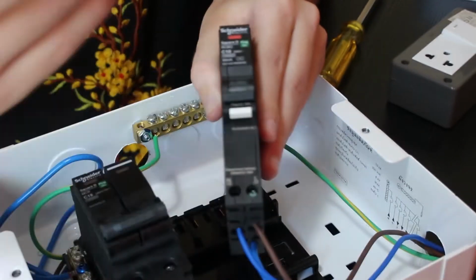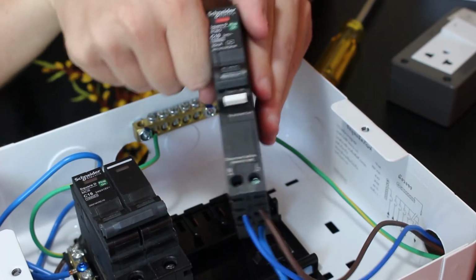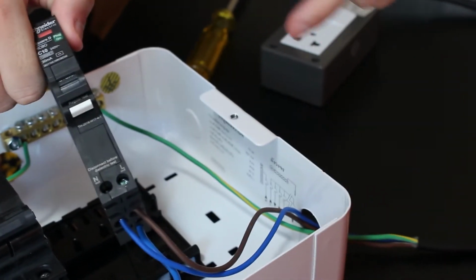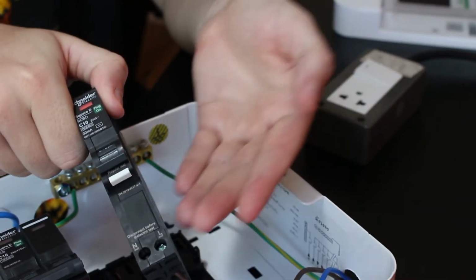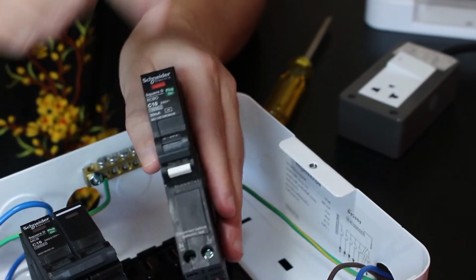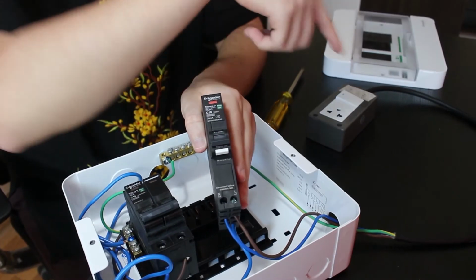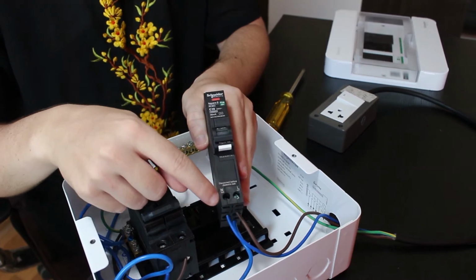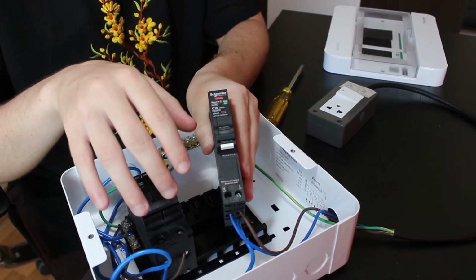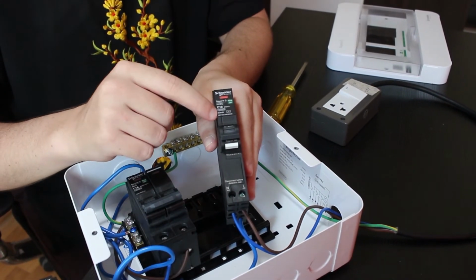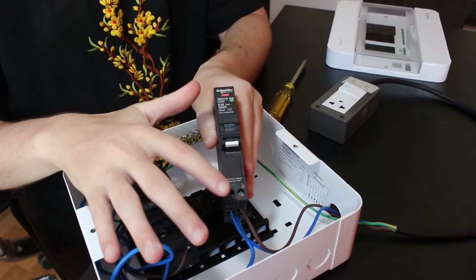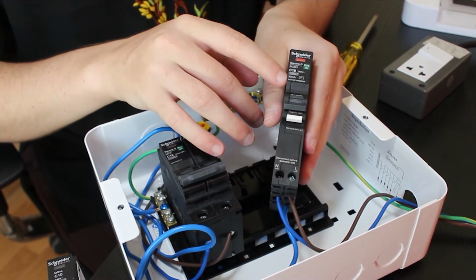In the case where somebody is touching the line cable, for example somewhere else, that person is going to become part of the circuit, and that current is going to go to the earth and so not come back through the neutral. So there you're going to have a difference. If the difference is greater than 30 milliamps, that one cuts. In that case, I got a 30 milliamp.